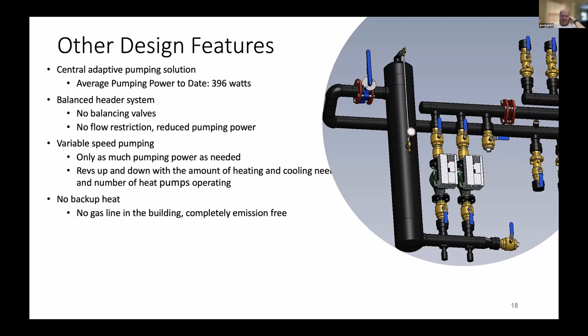The trick is here that we keep the pressure drop low. We have no balancing valves. The loop field boreholes are slightly shallower. They're only 400 feet, so we spread out the flow through more circuits. There are no restrictions in there, for example, no balance valves. And that helps us to keep the pumping power as low as possible. The trick is really to only pump as much as you need and to have smart pumps here to increase the efficiency. The entire building does not have any gas lines. It's completely emission free. The only gas line going in is for the emergency generator as a backup.